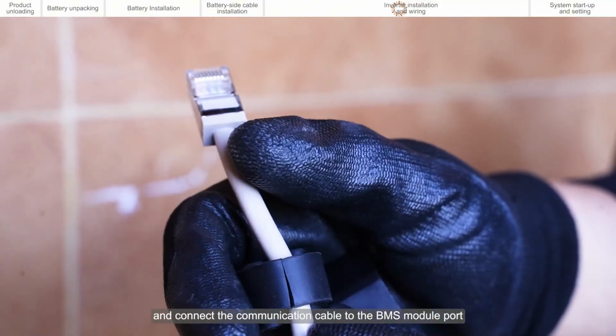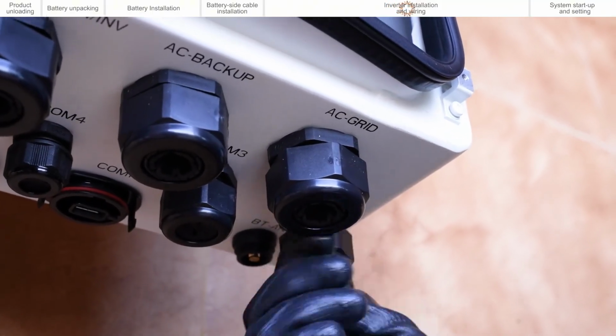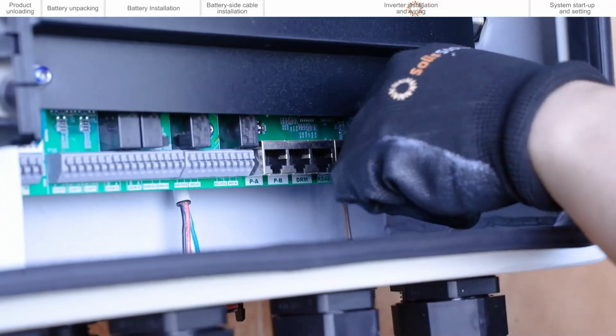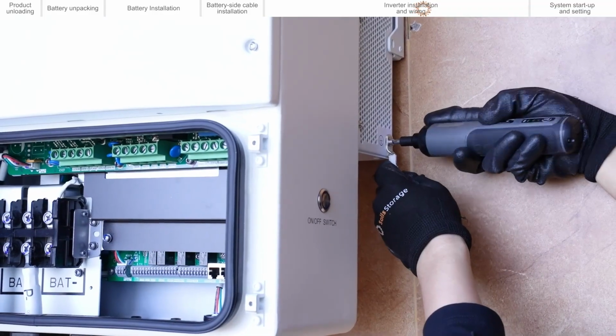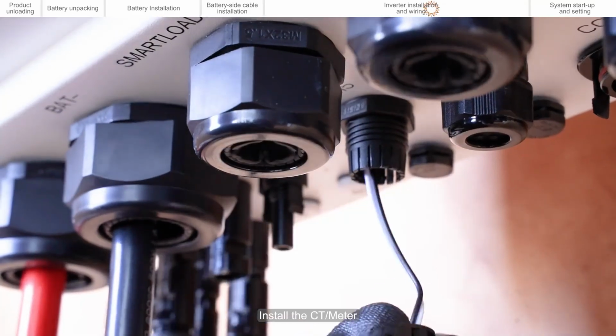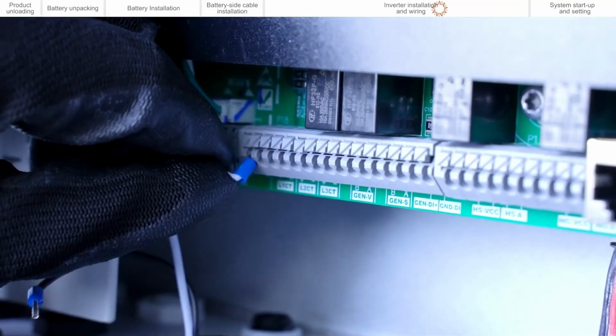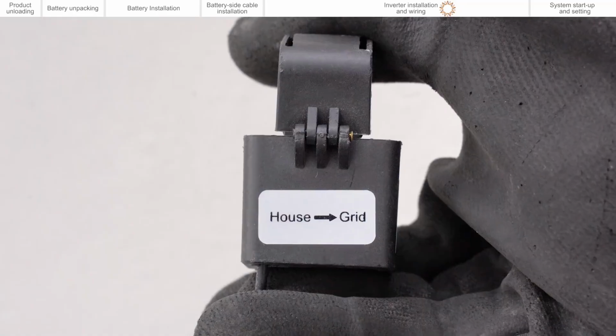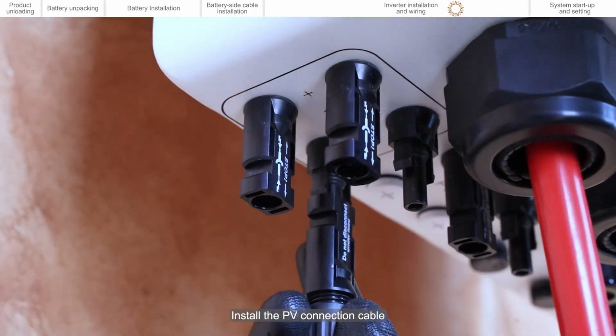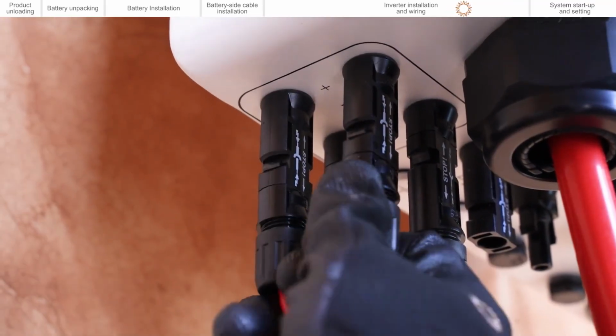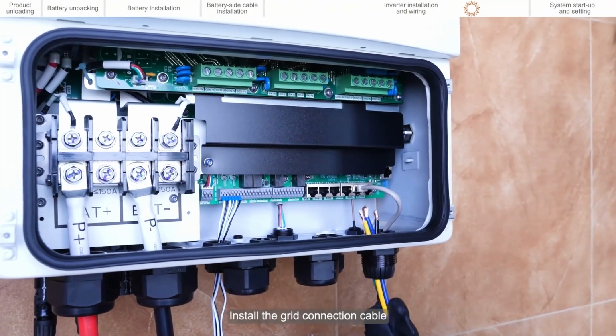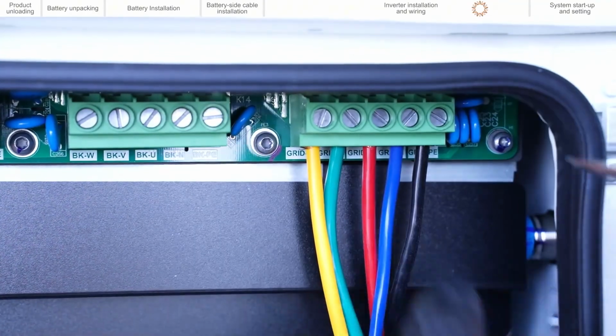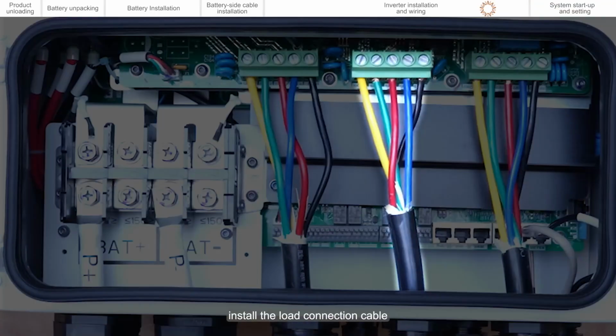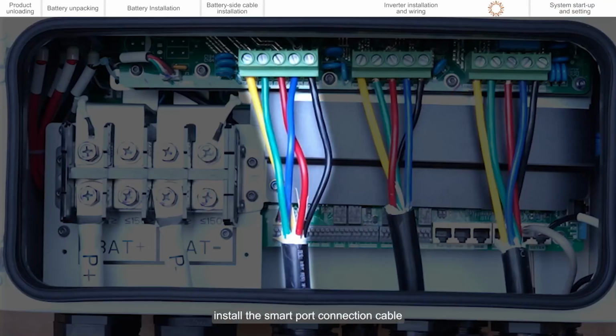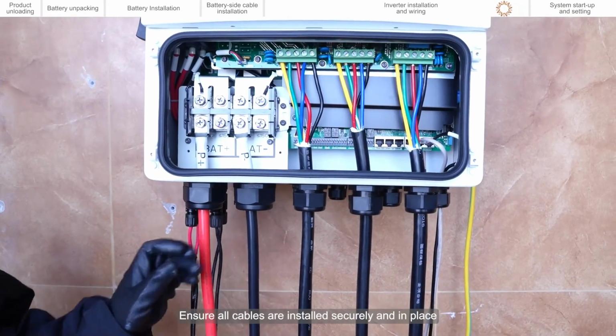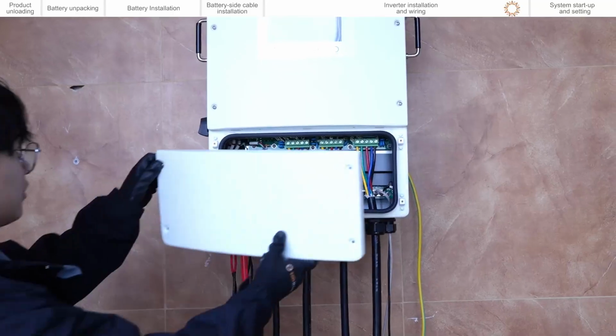And connect the communication cable to the BMS module port. Install the CT ammeter. Install the PV connection cable. Install the grid connection cable. Install the load connection cable. Install the smart port connection cable. Ensure all cables are installed securely and in place.